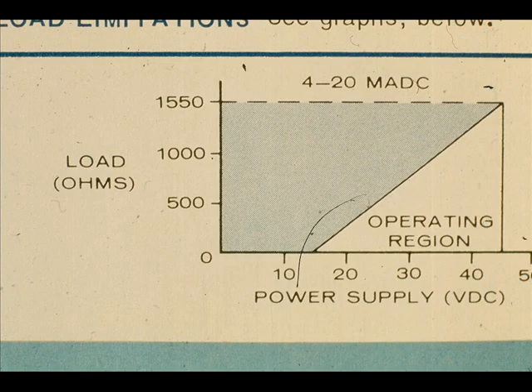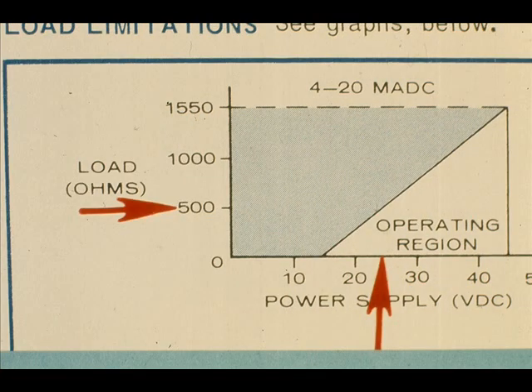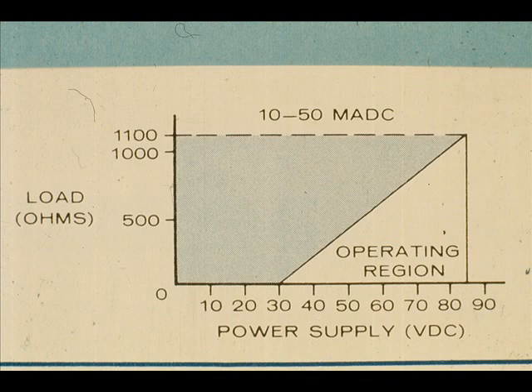The DC power supply required to operate the transmitter is dependent on the resistance in the circuit. The 4 to 20 milliampere circuit will operate from 14 volts DC with no load up to 45 volts DC with a 1,550-ohm load. With a 24-volt DC supply, the maximum load is approximately 500 ohms. The 10 to 50 milliampere circuit requires higher DC voltages.